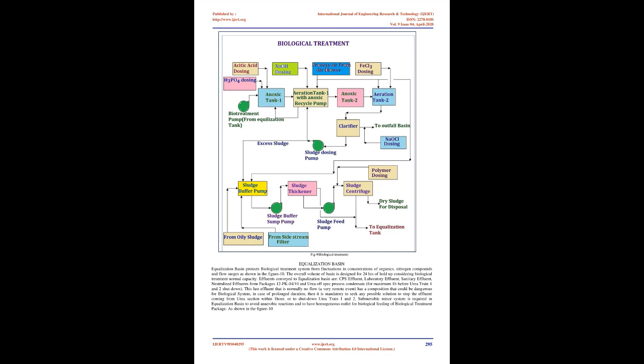PLC operation. The pumps are operated in hand or auto mode by switching the respective hand-off-auto selector switch provided on the HMI. Hand mode operation. In hand operation mode, each pump can be started and stopped manually from the HMI. Auto mode operation. In auto operation mode, the duty pump starts and stops automatically based on the following conditions. 1. The duty pump starts at high level in the sludge buffer sump. 2. The duty pump stops at low level.